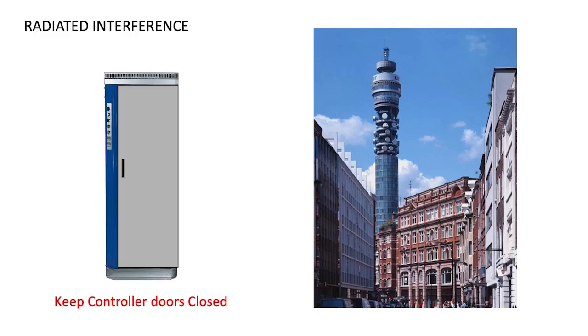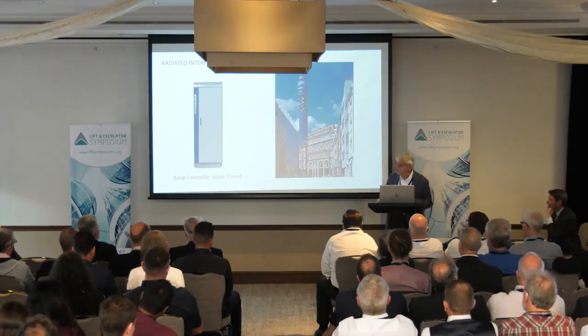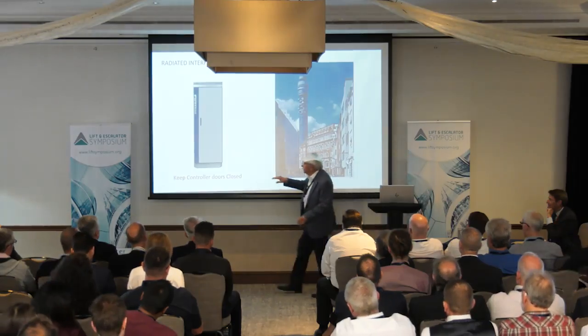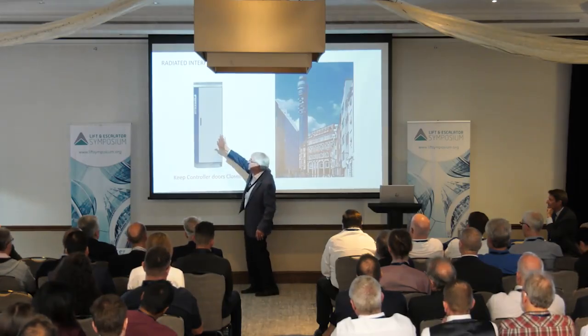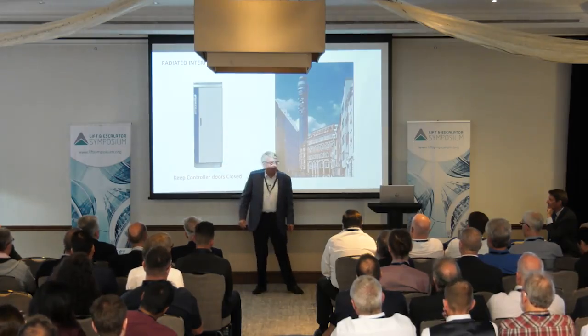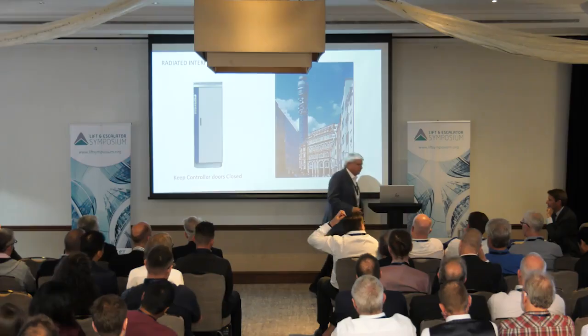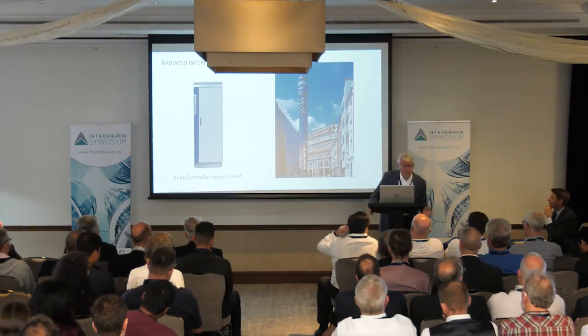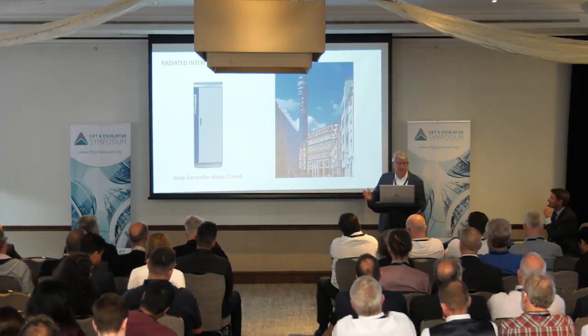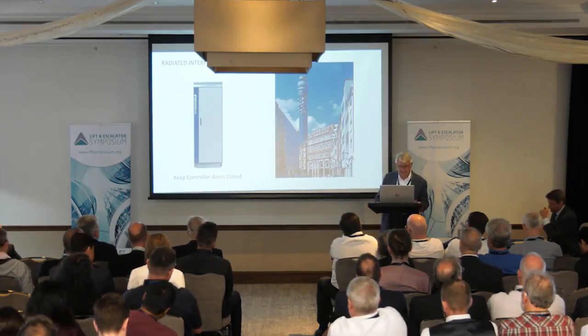People say, well, I need to open the cabinet door for better cooling. No, actually, that's not true. You get better cooling with the door closed because the air is designed on the cabinets to come in the bottom, through convection, go out the top, and you get a better chimney effect if you keep the doors closed. So keep the doors closed for cleanliness, for cooling, and for radiated interference.